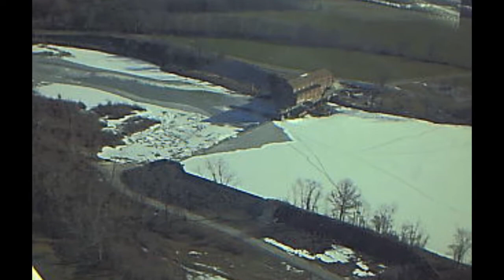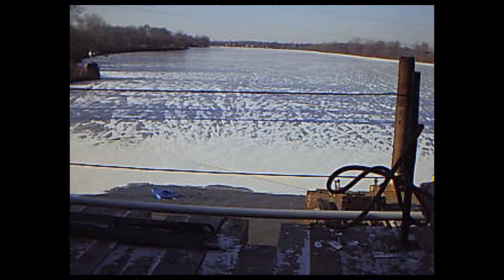The Auglaize hydro plant got off to a rough start in 1999. Heavy snow was followed by an overnight warm-up to 65 degrees. The rapidly thawing snow caused a sudden rise in the water level and moved a large flow of ice downriver and into the front of the power plant and the floodgate piers. The ice impact damaged the gates, trash racks, and concrete structures. They estimated the ice probably hit at about 35 miles an hour.